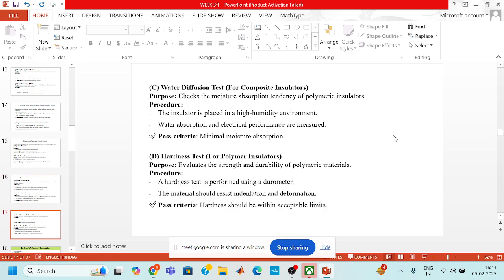Now, third is the water diffusion test. This test is used for composite insulators, and the purpose is to check the moisture absorption tendency of polymeric insulators. The insulator is placed in a high humidity environment, and water absorption and electrical performance are measured. And if there is minimal absorption of moisture, then the insulator will pass the water diffusion test.